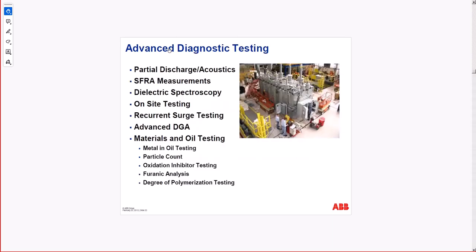So advanced diagnostic testing. Then base diagnostics are related to the resistance of the windings, balance of the windings. We do that with an actual micro-ohmmeter or ductor, another name for the same micro-ohmmeter. So we expect a maximum of a few ohms per winding. Then we have the ratio test of the transformer that also gives you the health of the transformer. Oil tests with the DGA, we're going to go into more detail about those. Each test has a standard that applies to the way the test should be done for the dissolved gas analysis.